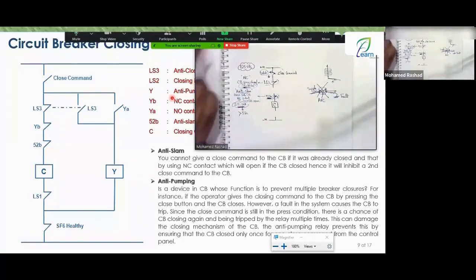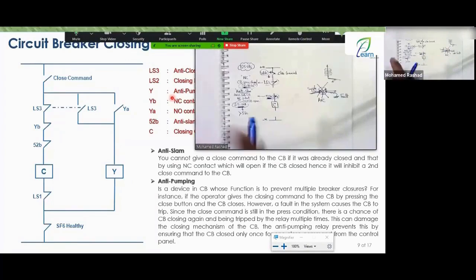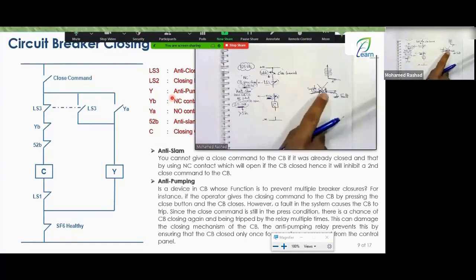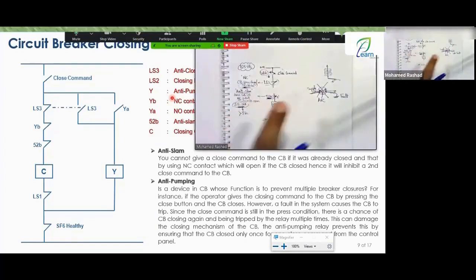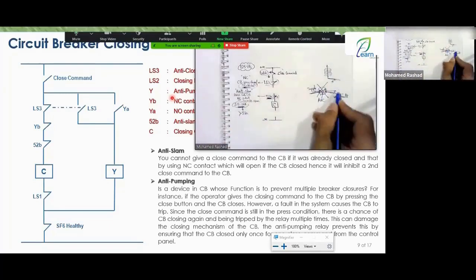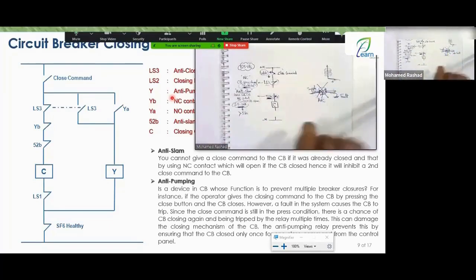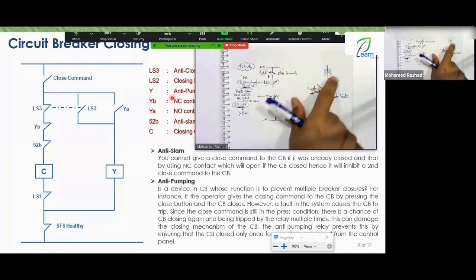As a maintenance person, they informed you, and you're heading to the station, which is an hour away. Imagine during that hour, every minute has how many 5-second intervals? It has 12 5-second intervals. So the breaker will be closing and opening 12 times in 60 minutes, which is 720 times, 720 times on the arc. And 720 times the spring is charging and discharging, and 720 times you're reaching the relay.